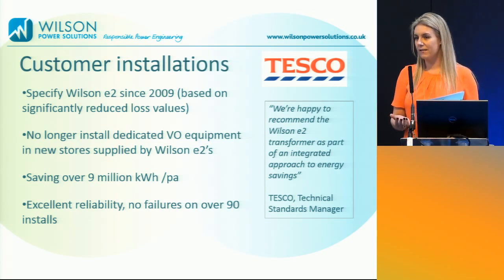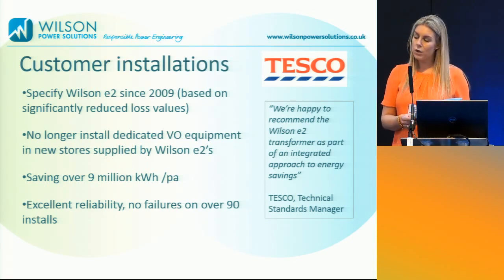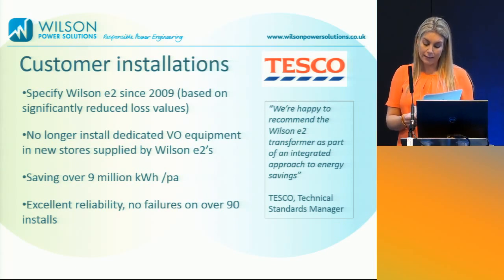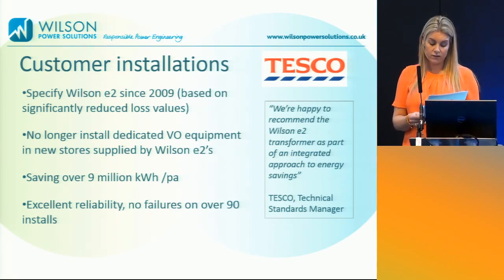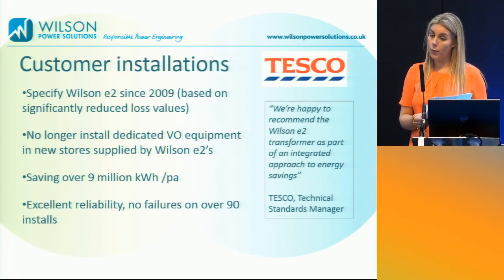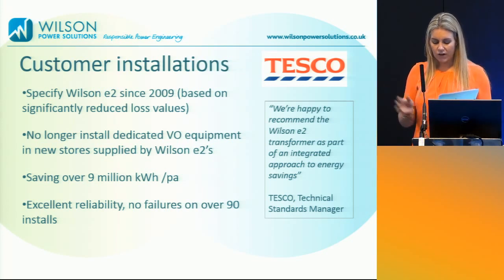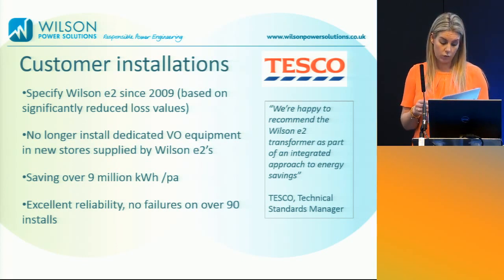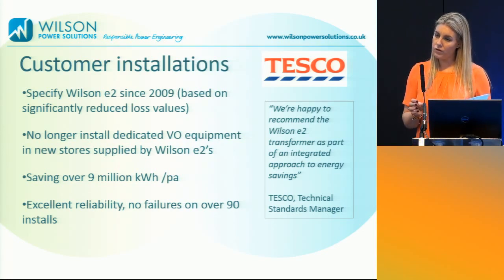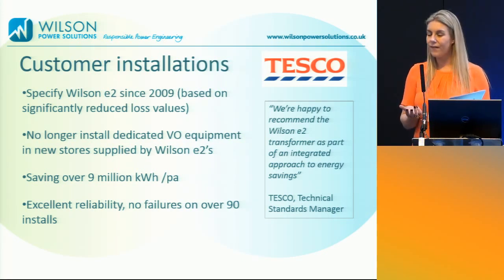So after over 90 installations with Tesco, with annual savings in excess of 9 million kilowatt hours per year, Tesco recommends the Wilson E2 as part of an integrated energy efficiency approach. Just to highlight the extra capex of this product compared to a standard loss transformer, it would be paid back in 18 months. And that's just through the transformer losses alone. So over a 25-year estimated life, you'll save over £70,000 in running costs just through those losses alone in the transformer.